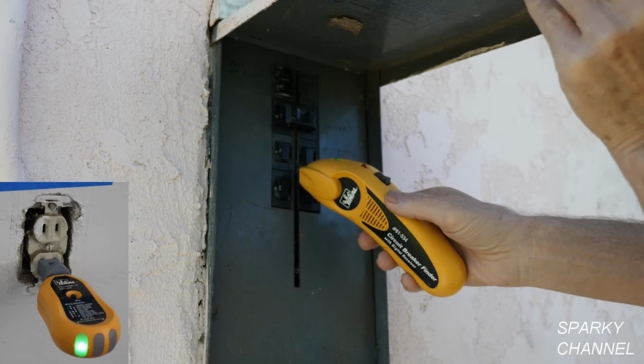Here we are back at the receptacle. Notice all the lights are off. I have a piece of blue tape above this receptacle, and I'm going to put a piece of blue tape for every receptacle that I find that is off right now, and that'll mark all the receptacles on this particular circuit. Here's another receptacle in the same bedroom, so I'll plug it in, and this is one of them.